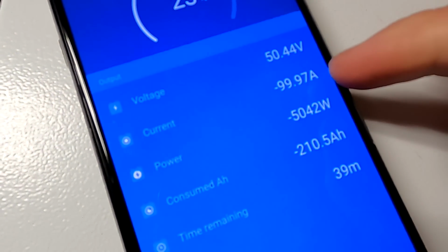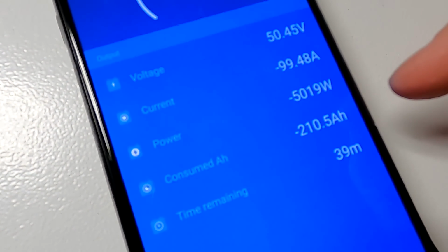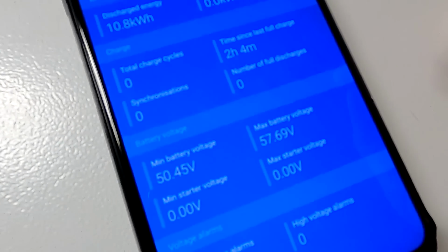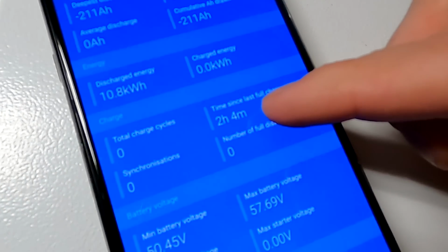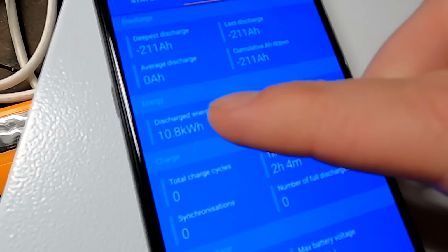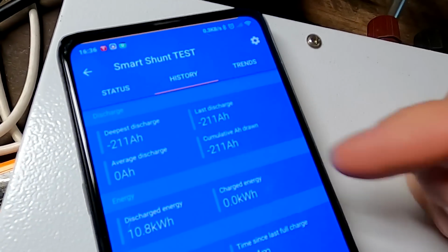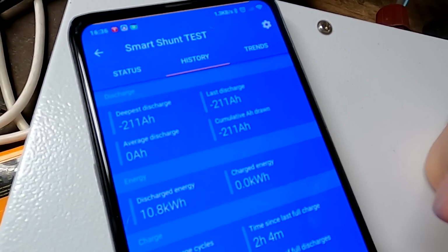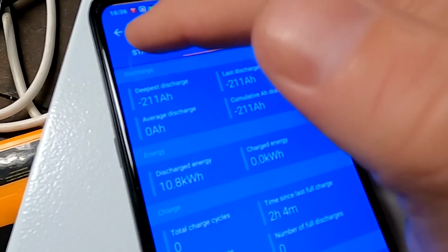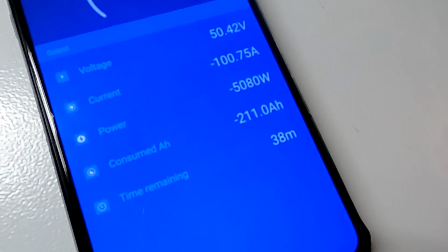So still discharging with around 100 amps, 5 kilowatts, and we are 2 hours and 4 minutes into the test. 10.8 kilowatt hours, 211 ampere hours discharged so far. It will be another half an hour.